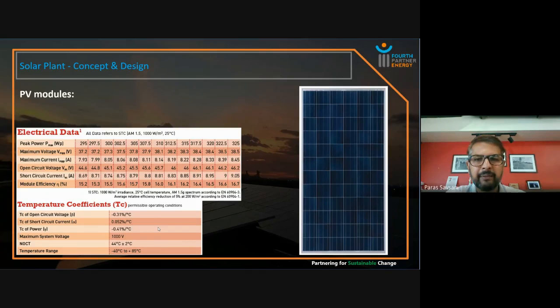For example, if we look at this first column for easy understanding, for a 295 watt peak module, what is the maximum voltage and maximum current? It's 37 volt DC generated per panel, and the current can generate 7.93 amps as a max. There are two other parameters which are the maximum or breakdown limits: 44 volt DC is the open circuit voltage, and the short circuit current is 8.69, which is the highest possible. If it goes beyond this, there will be damage.